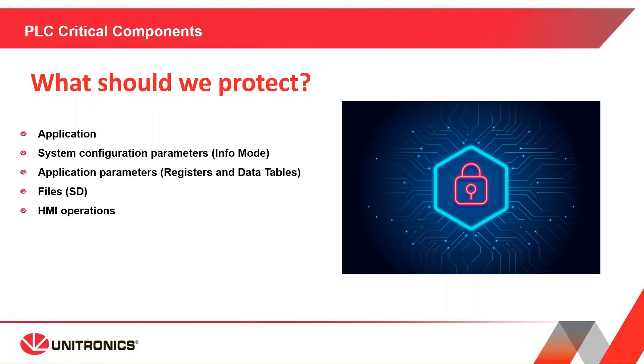For PLCs, what should we protect? First, we must protect the application, because it's the easiest way to cause damage — someone can download an empty application and the entire machine becomes useless. We also need to protect system configuration parameters like IP addresses, com ports, and communication protocols. For Vision and Samba, that's what we call info mode. Additionally, application parameters such as set points, limits, and maximum temperature values, as well as data tables, SD files, and HMI user operations directly from the screen.